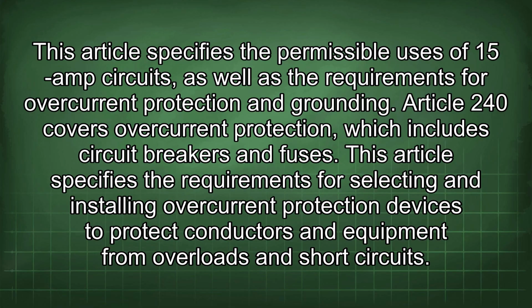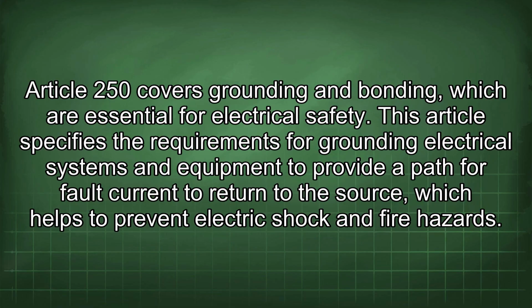Article 240 covers overcurrent protection, which includes circuit breakers and fuses. This article specifies the requirements for selecting and installing overcurrent protection devices to protect conductors and equipment from overloads and short circuits. Article 250 covers grounding and bonding, which are essential for electrical safety. This article specifies the requirements for grounding electrical systems and equipment to provide a path for fault current to return to the source, which helps to prevent electric shock and fire hazards.